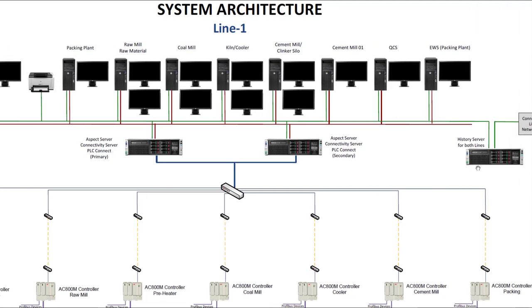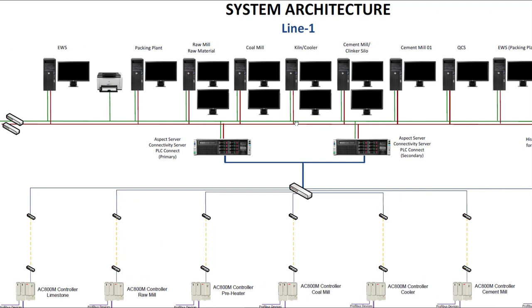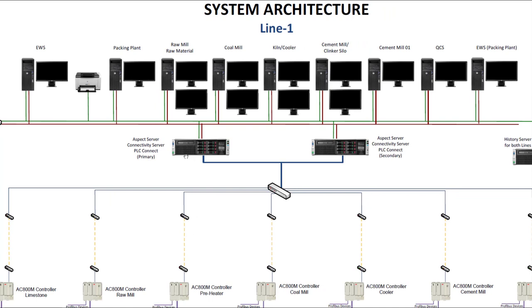We have a pair of servers — operator station servers — which have redundancy, because if one server goes down the next will take over the process. The operation, monitoring, and control of the process is very critical; we do not want to stop the process. This is why we introduce redundancy. We have redundant servers — one is primary and the other secondary. These servers read the data from the PLCs.